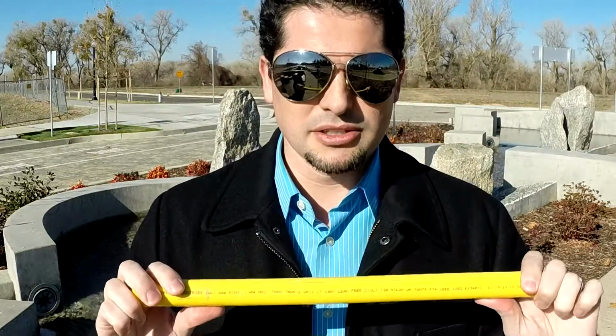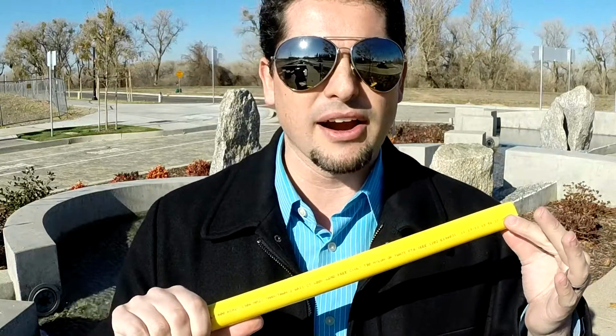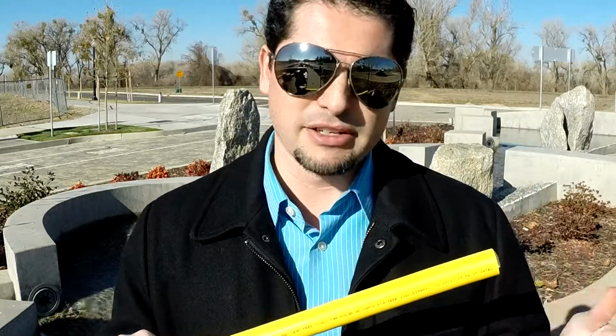So as we look into ampacity further, we find out that those tables we look at, that everybody uses the same number for the same cable of ampacity, have all these assumptions at the bottom of the table and even at the top in the description. Some of those assumptions are physical configuration: if this cable is underground or above ground or in a conduit, or if it's open to free air, there are different tables or there are adjustment factors for that.